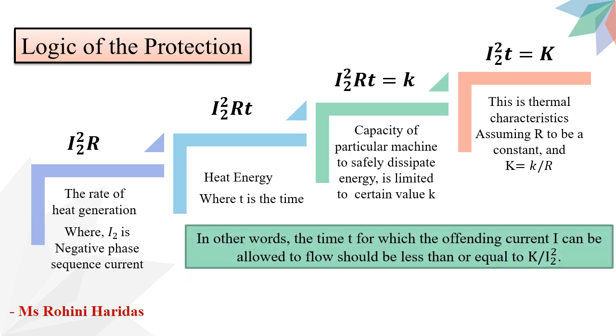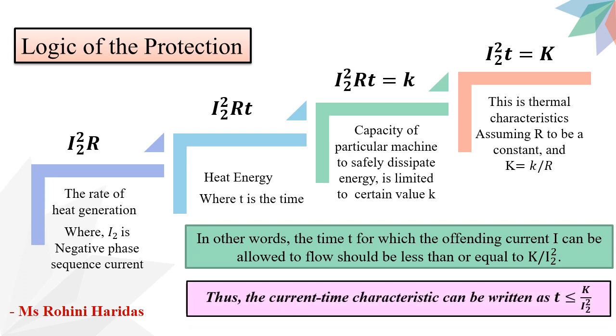In other words, the time T for which the offending current I₂ can be allowed to flow should be less than or equal to K/I₂². Thus, the current-time characteristic can be written as T ≤ K/I₂². This characteristic is similar to that of the inverse time over-current relay. Thus, an inverse time over-current relay which is fed with the negative sequence component of the stator current gives protection against unbalanced loading of the generator.